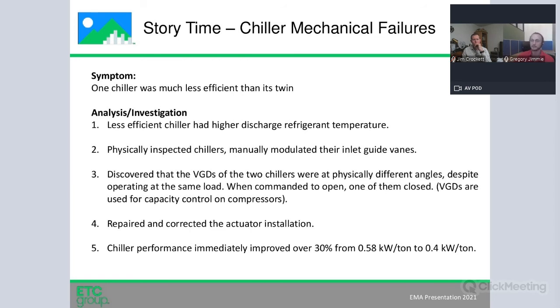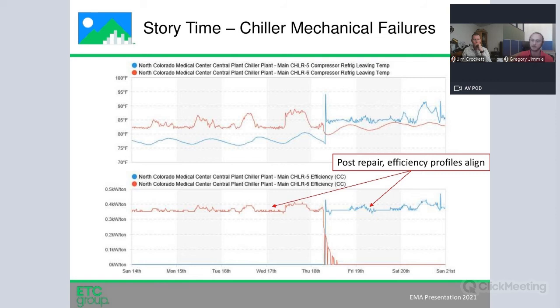And it was pretty amazing because, the same day, the same chiller, we saw a 30% change in its energy consumed. Now, after we made the repair and made that change, it was pretty much right in line with its sister or twin chiller. You can see these chillers now are pretty much a flat line. I just picked this about a week after the repair had been done, and for all intents and purposes, they act the same.